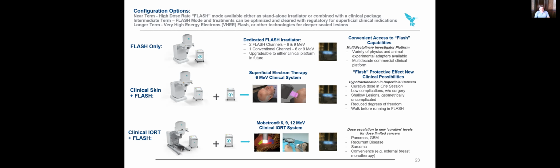If you buy the clinical system, what we do to be able to maintain our regulatory certification is we have the flash cabinet, which is our control cabinet for the 3 channels, sold separately as an add-on. So if you look at the top row, the flash only, that flash cabinet gives you 2 flash channels, 6 and 9 MeV, and 1 conventional channel. So that lets you have your standard beam at 10 gray a minute. That's a normal dose rate in a conventional machine, and then 2 at these very high dose rates.